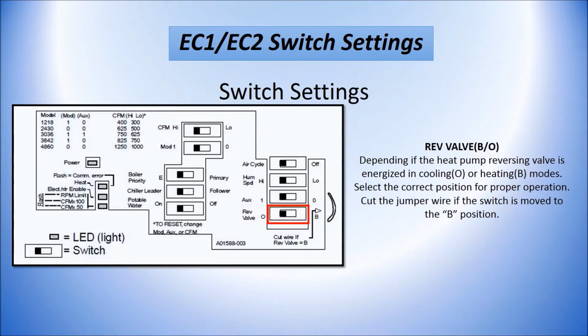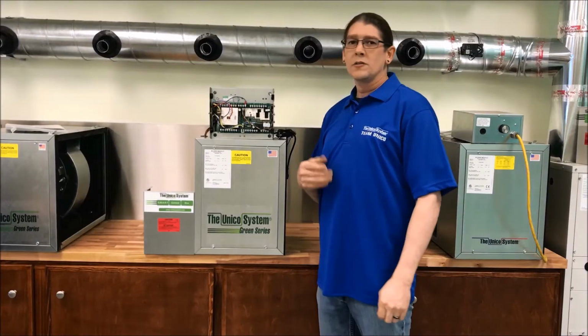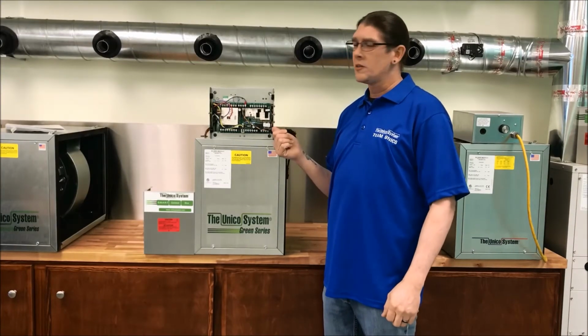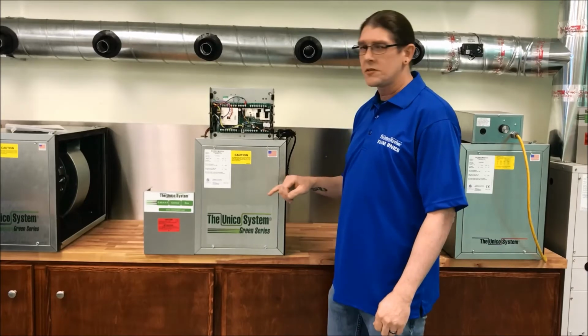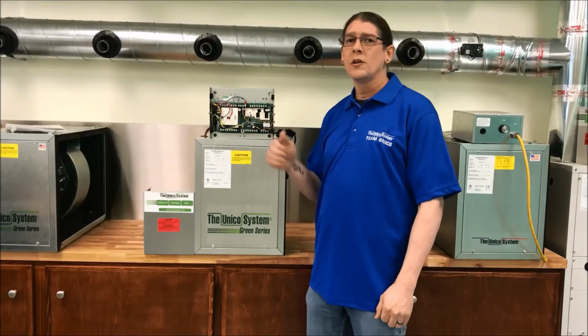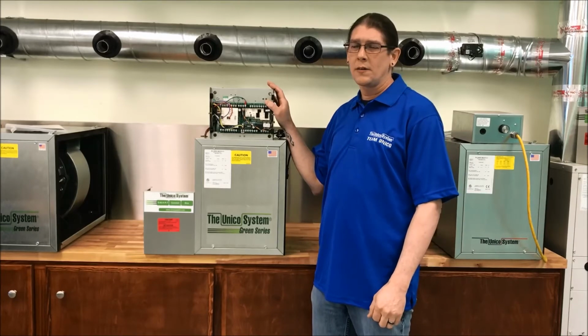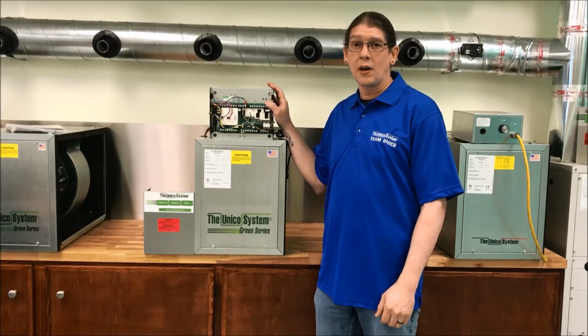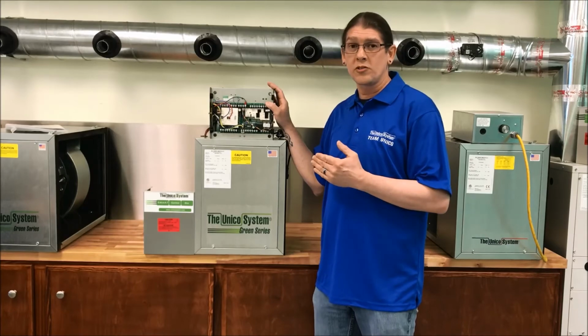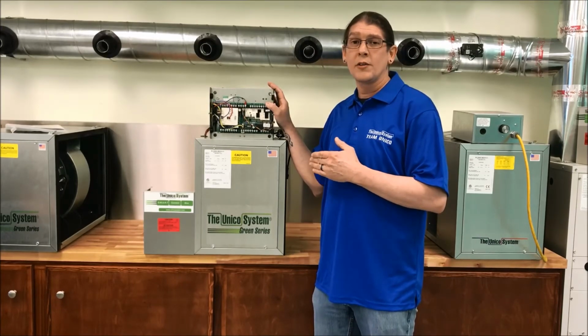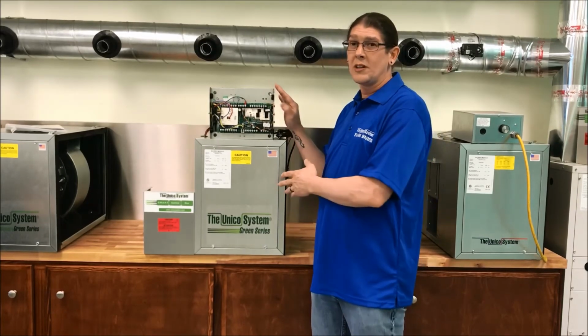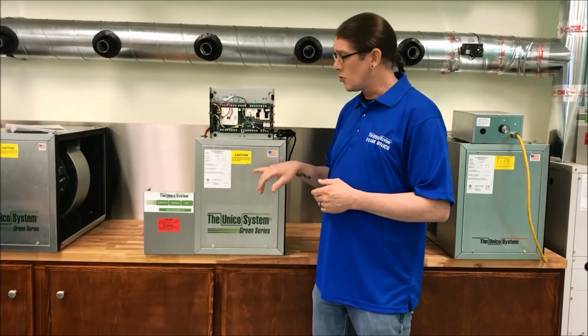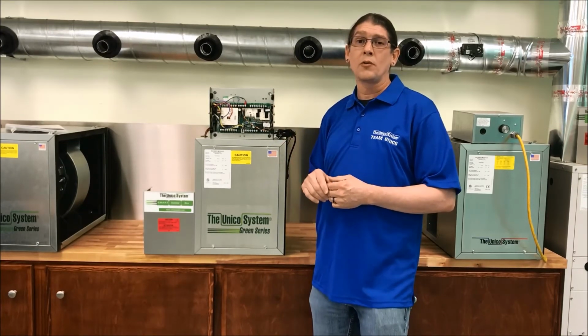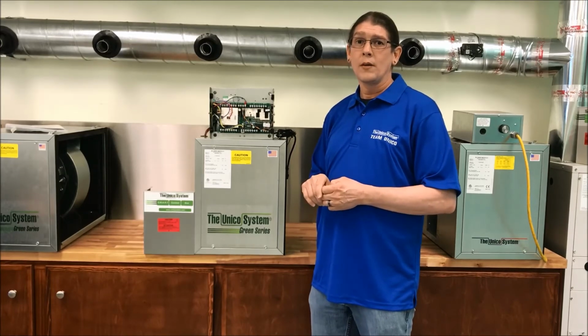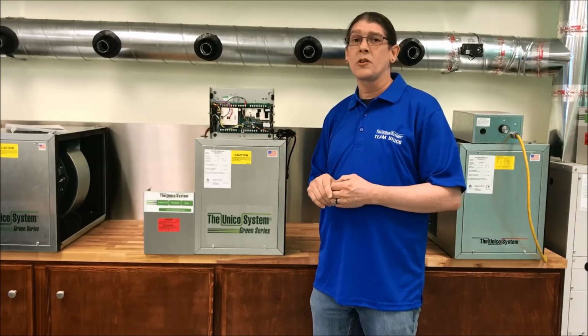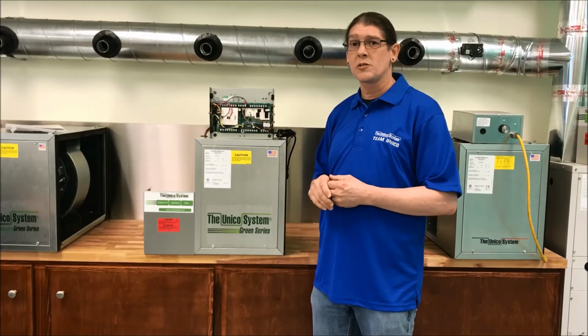If you have it in the B position, be sure to cut the jumper wire. So there you have it. That's how you set the switches on the EC board. Anything that is a green series is going to have an EC motor and this smart control box in it. They're all set for 1218 out of the factory. So make sure you go through all the switch settings, make sure everything's set up correctly. If it's set up as a 1218 and your unit is not a 1218, like this one's a 2430, that would cause the motor to spin in the wrong direction. You will get no airflow. So to eliminate problems when commissioning a unit, make sure that you set all the dip switches before powering the unit.